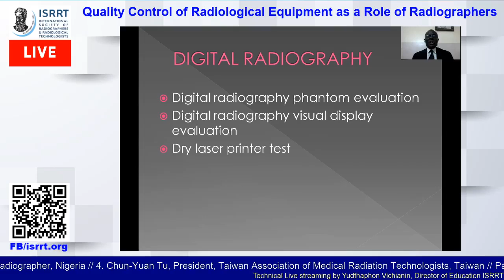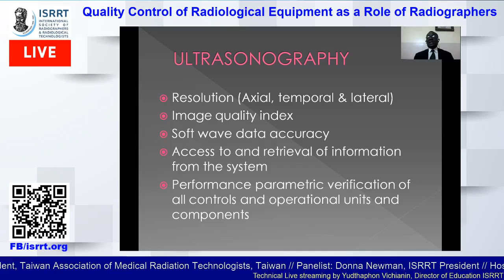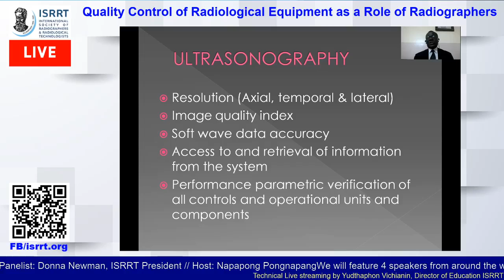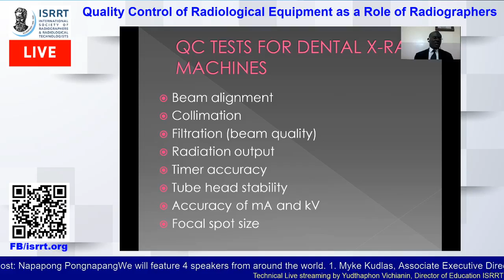In ultrasonography, the major criteria are the measurement for resolution, which includes the axial, the temporal, and the lateral resolution, the image quality index, the software data accuracy, the access to and retrieval of information from the system, performance parametric verification of all controls and operational units and components. The quality control tests for dental X-ray machines include beam alignment, collimation, filtration, radiation output, time accuracy, etc.